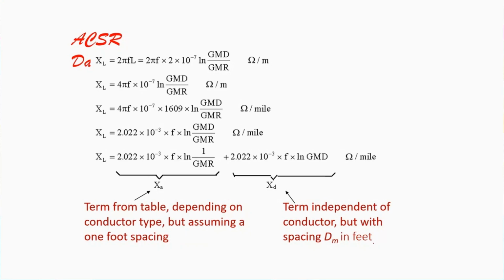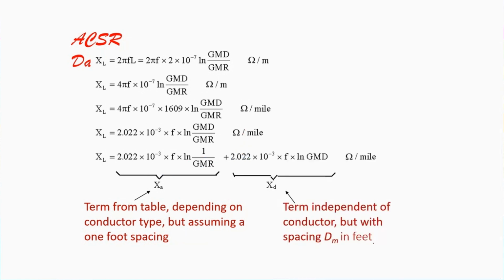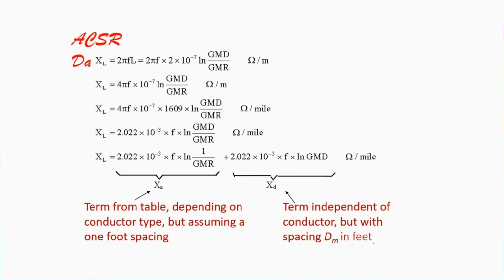XA here is something provided in the manufacturer data sheet. It's only one part of the inductance. They did this because if we go back to the simple equation we have for inductance, it's 2 times 10 to the minus 7, ln GMD over GMR. This is the equation we know we are using. If we want XL, we multiply by omega L, 2 pi F. So it's easy, but for the manufacturer, they want to provide you with information regarding this conductor.